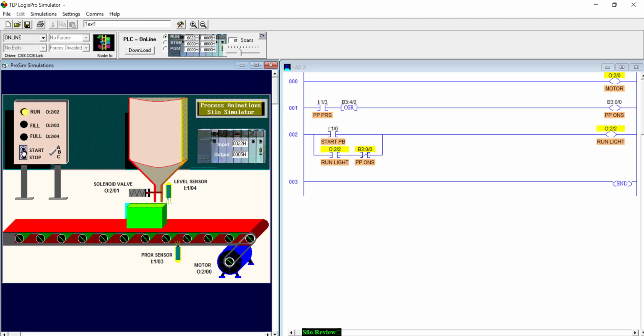So I want you to think about this circuit when you're developing your program to stop the box, because you've got to stop that box as soon as that sensor comes on. If there was a problem, say, where that sensor was too close or too far away, what could we do? We could put even a time delay in there if we had to. But if I remember right, this program's set up pretty well. As soon as that sensor comes on, that box needs to stop, and that motor stops right on the same spot every time. So we're in pretty good shape there.